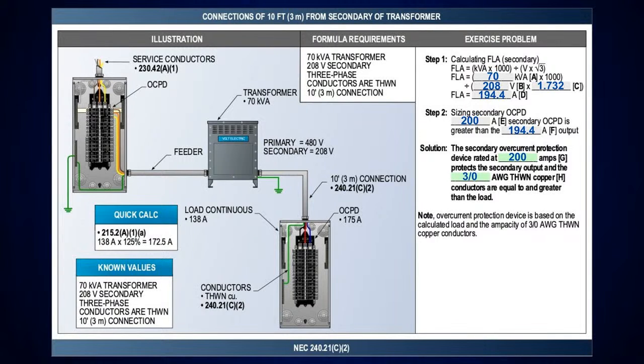Well, if I want to size the overcurrent device for that, I'll go over and look at table 240.6(A) for the standard ampere rating. The next size above that is 200 amp. And then if I look at table 310.16, 75 degree C column, 200 amps is for a 3/0 conductor. So in this case, I just sized it real quick: I need a 200 amp overcurrent device and 3/0 copper conductors.